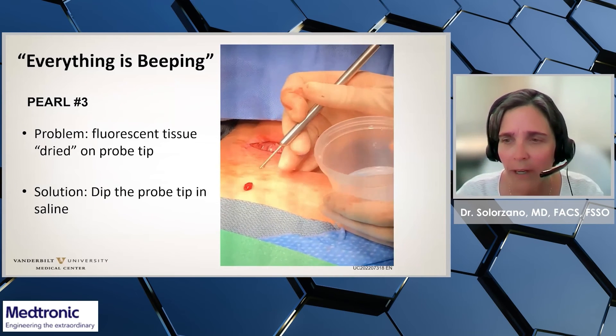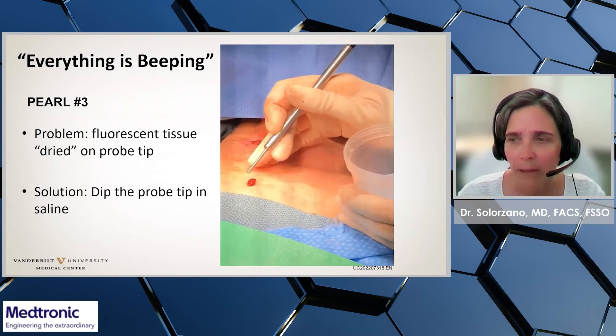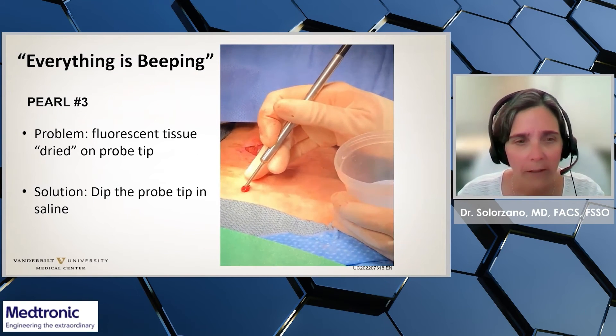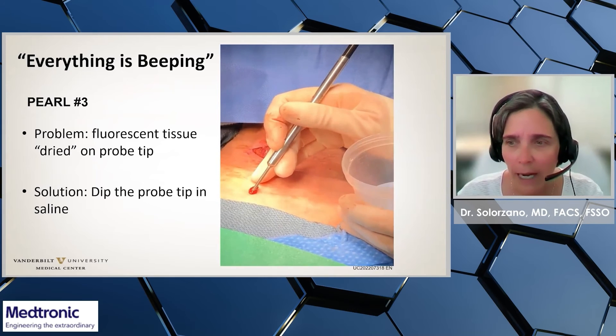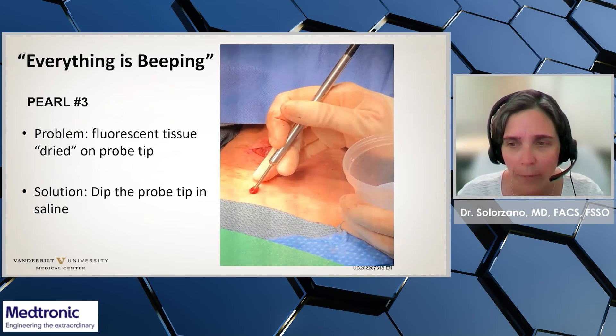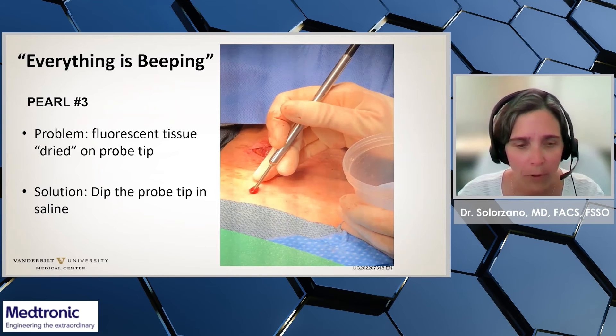What about when everything is beeping? This can happen if the probe has been sitting idle and fluorescent tissue has dried on the probe tip. To fix it, you can dip the probe in saline or water.